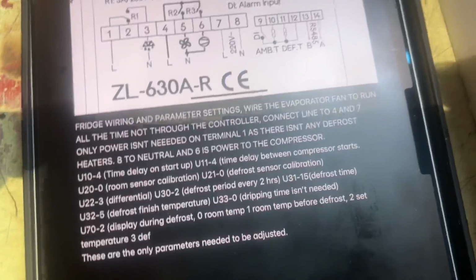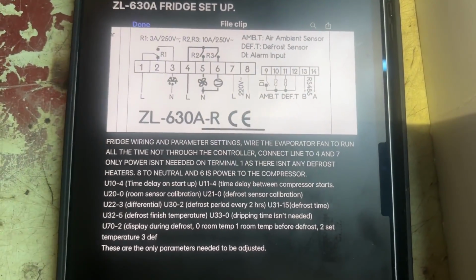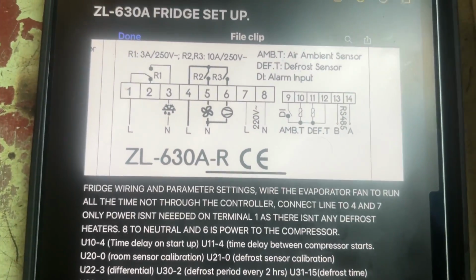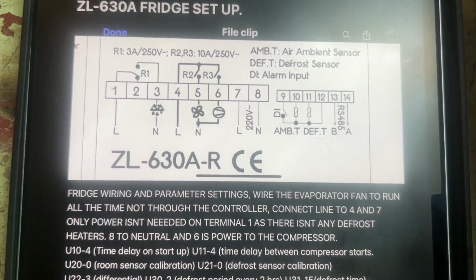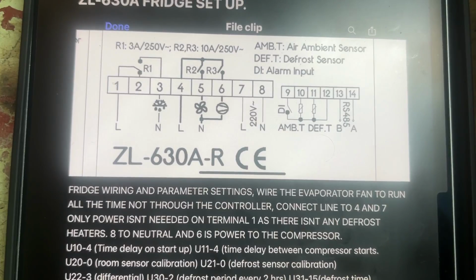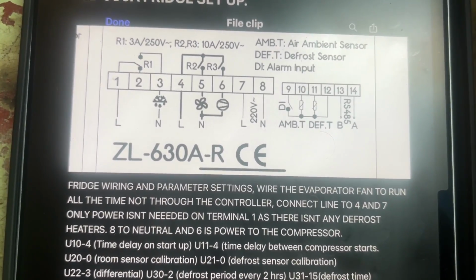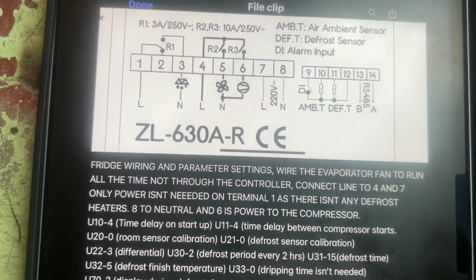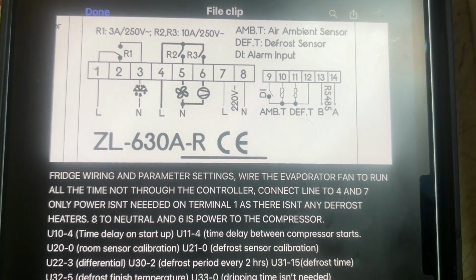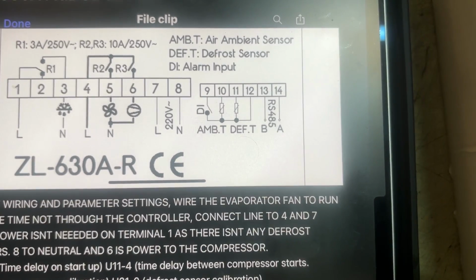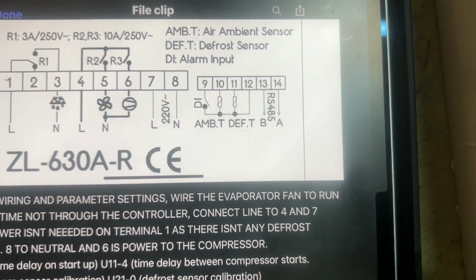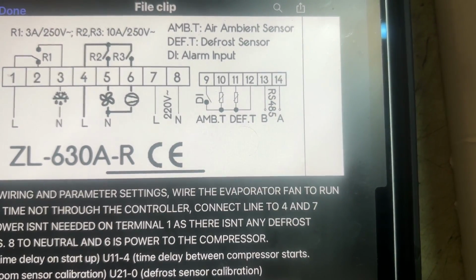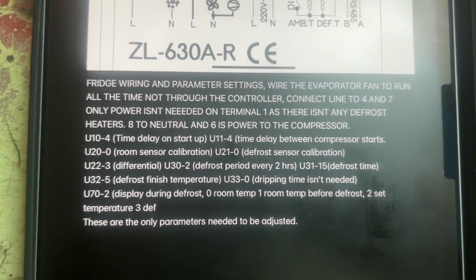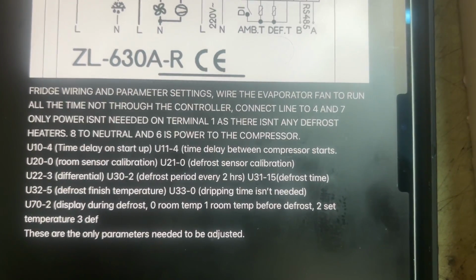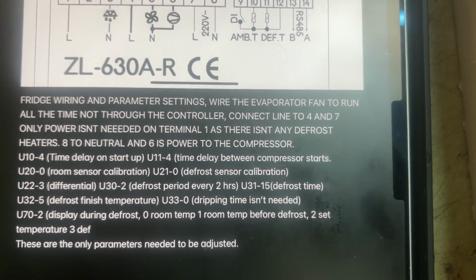And I'm just going to hover over my iPad, if I can get that. I'll leave that there, so that let me turn my light off. So I'll show you there. So when it's a fridge, we just need power on 4. Compressor goes to 6. We need power on 7. Neutral on 8. The rest we don't need, because there's no defrost. We're not running the fans through the controller, and the sensors, we just have the ambient sensor, the room sensor on 10, defrost sensor on 11, and the other sides of the sensors on 12. And I've just written down there, just hover over it for a while so you can see that.